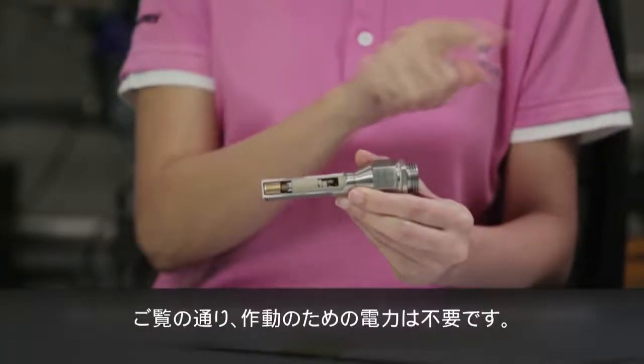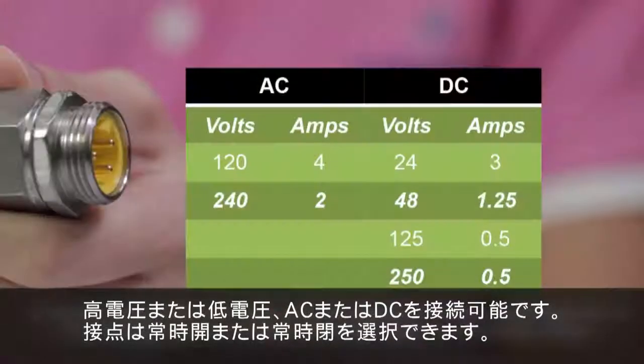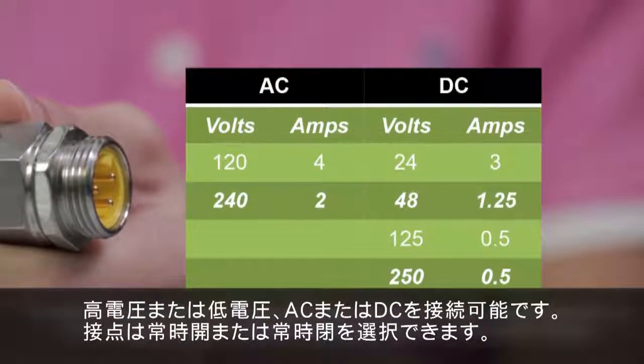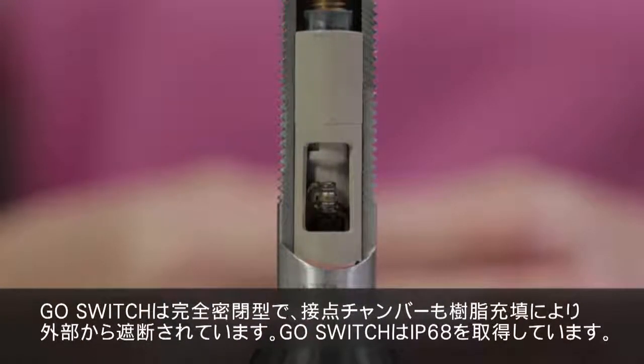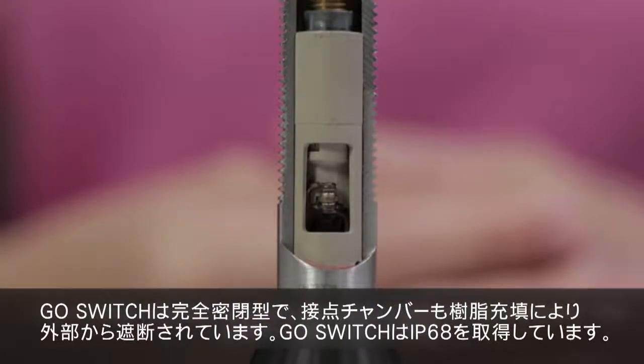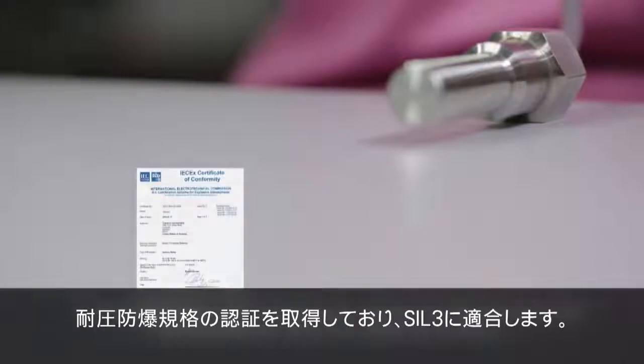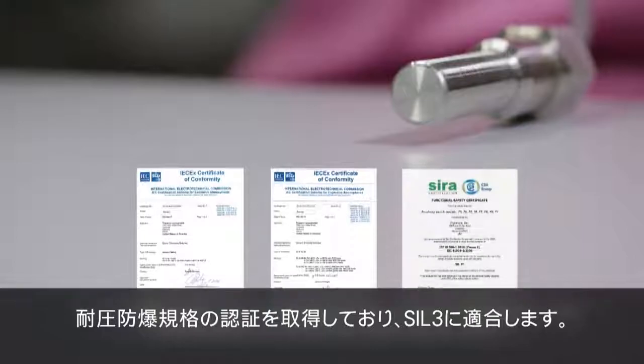As you can see, it does not require electrical power to operate. It can be used with both high and low electrical loads, wired with AC or DC voltage, and connected normally open or normally closed. GoSwitch is hermetically sealed — the contact chamber is potted and sealed from the environment. The switch is rated up to IP68. It has the widest operating temperature range of minus 60 to 204 degrees Celsius. It is certified for use in explosion proof and intrinsically safe environments, and it is rated up to SIL 3.